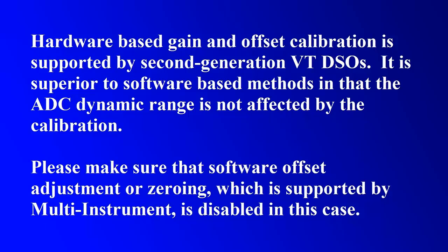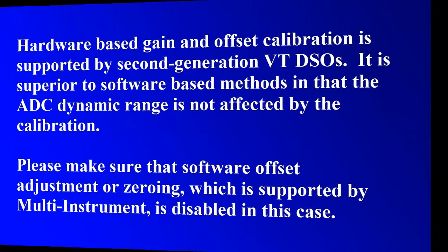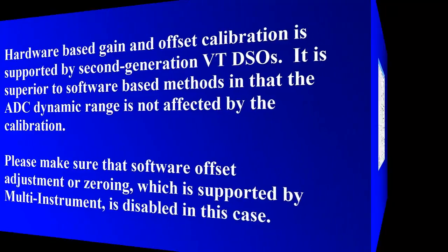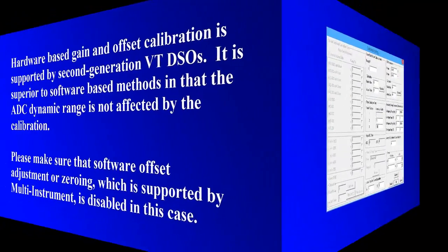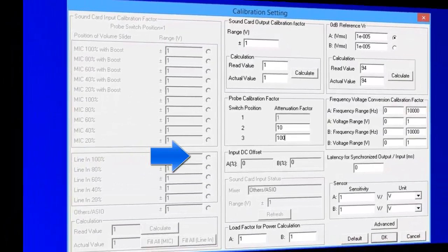Please make sure that software-based offset adjustment or zeroing, which is supported by Multi-Instrument, is disabled in this case. You can go to Setting, Calibration, and make sure that the input DC offset for both channels is 0%.